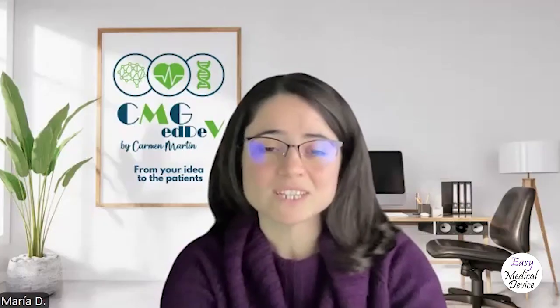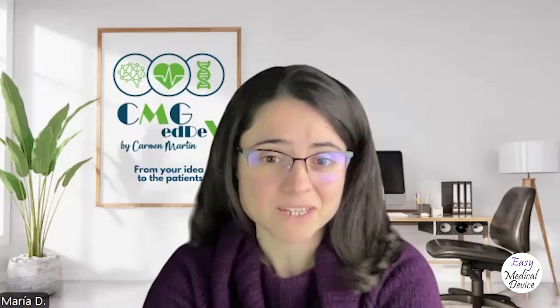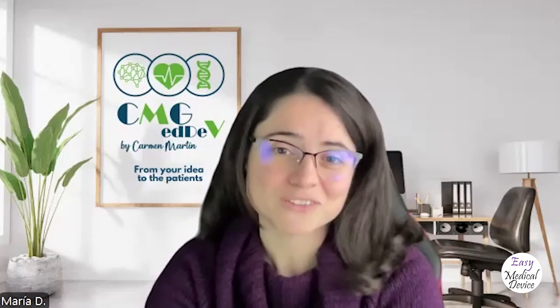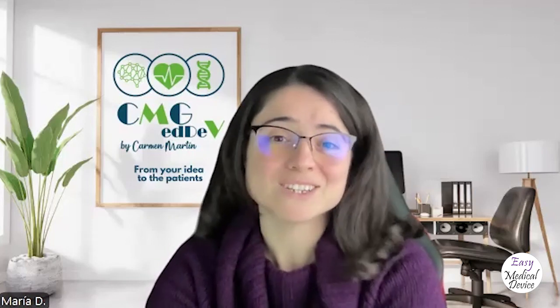So is a PCCP something that, as soon as it's approved, can stay like that forever? Or can we modify it? How does this work? Yeah, it's the same as the rest of the documentation and the rest of the medical device. I have heard recently that you can consider your PCCP as a medical device by itself. So if you modify it and it's a significant change, you also have to notify the FDA and create a new submission for the new plan. Interesting. So it's considered like the label and IFU, part of the medical device. So if you modify the PCCP that was approved before, it's like a new submission.